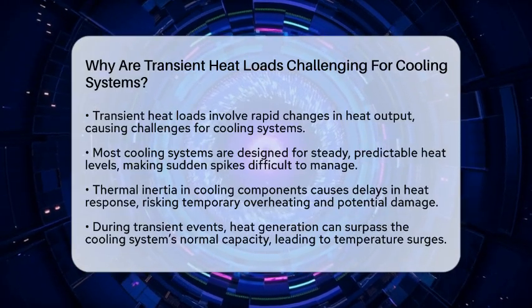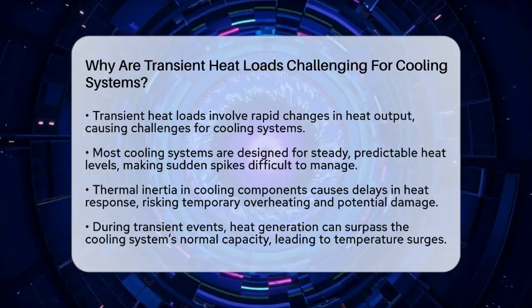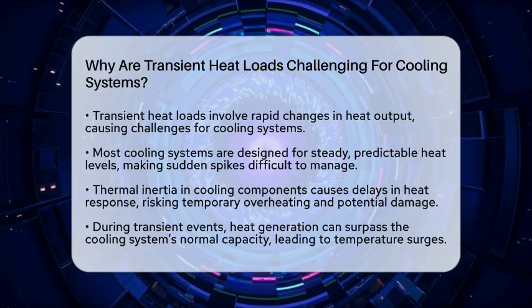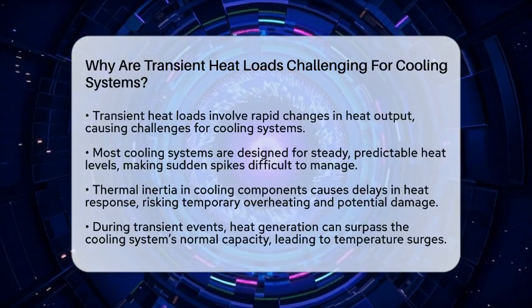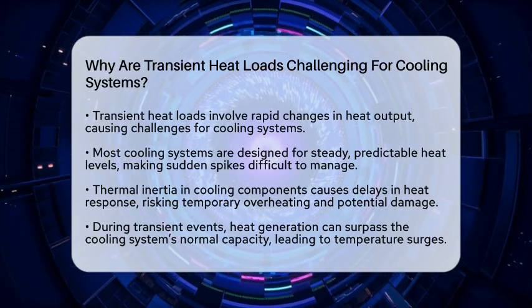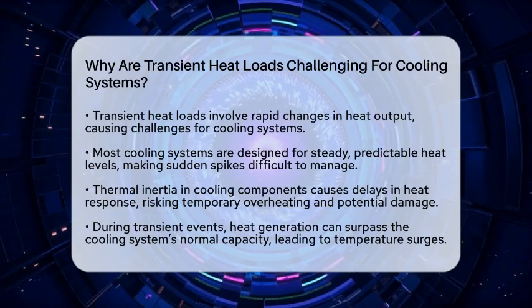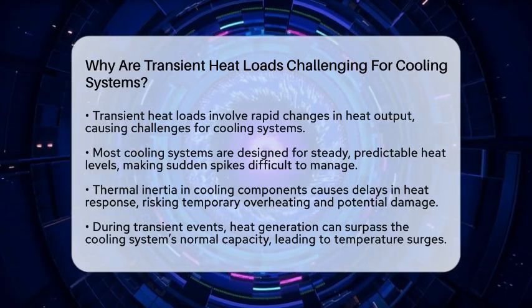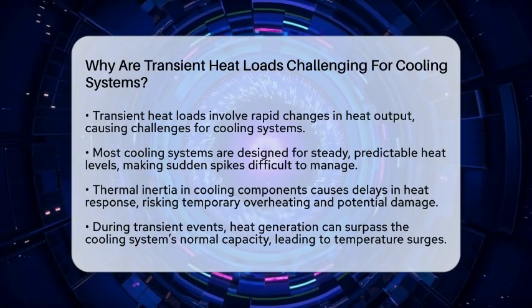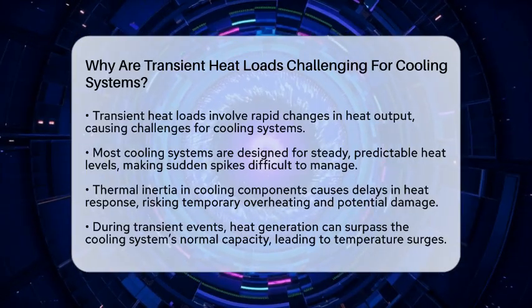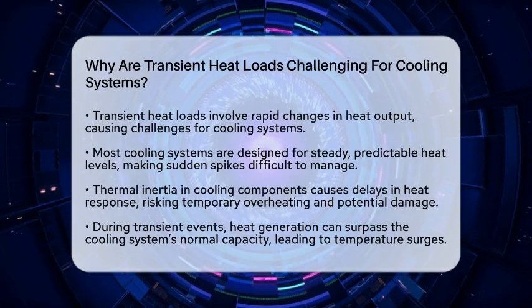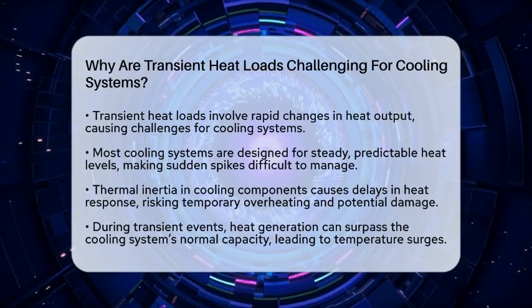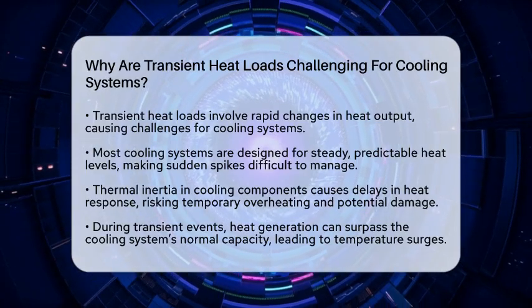These are tricky because most cooling systems are designed to handle steady, predictable heat levels. But when heat spikes happen suddenly, it throws off the system's balance. Cooling systems have something called thermal inertia. This means they take time to respond because they store heat in their materials. If a component suddenly heats up, the cooling system can lag behind, causing temporary overheating.